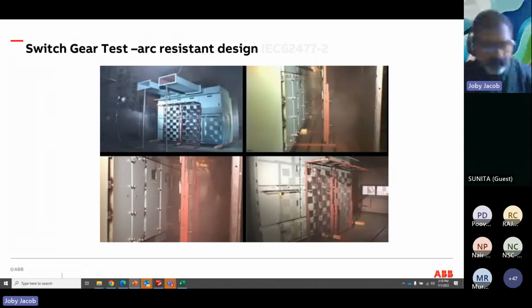But when it comes to the switchgear part, what kind of test is there? The arc resistant test as per IEC 62477. This is a real test environment where our panels are getting tested. When an arc occurs due to some internal failure or short circuit or physical failure, normally the heat travels up, right? So every panel should have a heat vent. When you are doing a switching operation, where should you stand? Particularly if you are operating an RMU or anything like that, don't stand on the side, because probably the explosion vents are at that side.